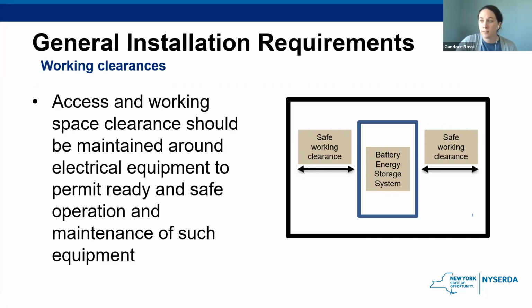So here we have the working clearances. Access and working clearance space shall be provided and maintained about all electrical equipment to permit ready and safe operation and maintenance of such equipment. So this should be done in accordance with NFPA 70 or the National Electric Code and the manufacturer's instructions. So the clearance for working on equipment should be 3 feet according to NFPA 70, and these clearances should always be unobstructed. Fire departments that may go out to a site visit should notify the owners of the equipment if they're not compliant with these regulations.